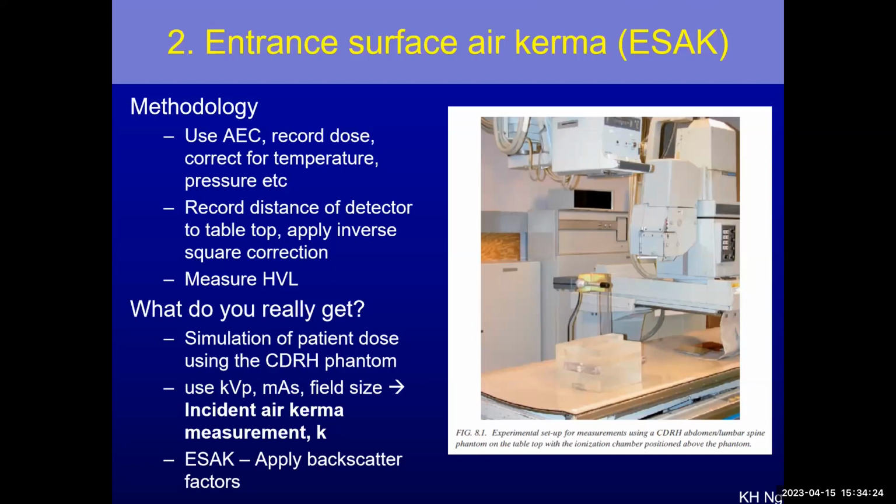Well, the TRS is quite particular about correction for temperature and pressure, but in practice, those of us in diagnosis don't quite bother. But in therapy, yes, you need to correct, particularly for ion chamber. But today we use solid state detector. That is not an issue anymore.